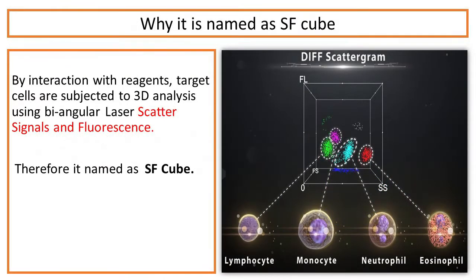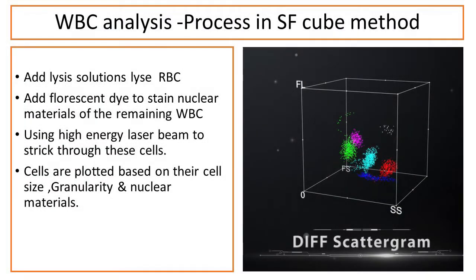Why is it named SF Cube technology? By interaction with reagents and fluorescent dye, target cells are subjected to 3D analysis using angular laser scatter signals. Therefore, it is named SF Cube. Let's see the white blood cell analysis process in the SF Cube method.